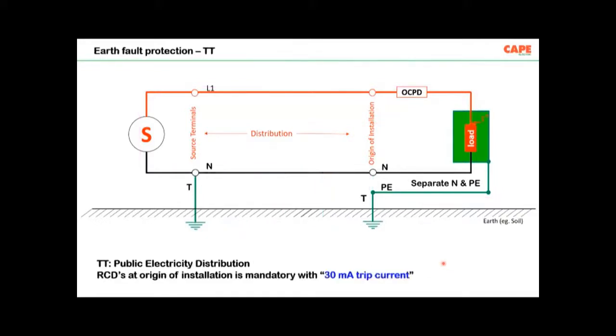In the next network, which is called a TT network, the source is earthed to an earth electrode in soil. The equipment side is connected to a different earth electrode in soil. Imagine there is a fault. The fault current is returning back to the source through the earth electrode, through the soil. So through the equipment earthing, it goes to the earth electrode. Through the system earthing, it comes back to the source, and finally the fault loop circuit is closed.